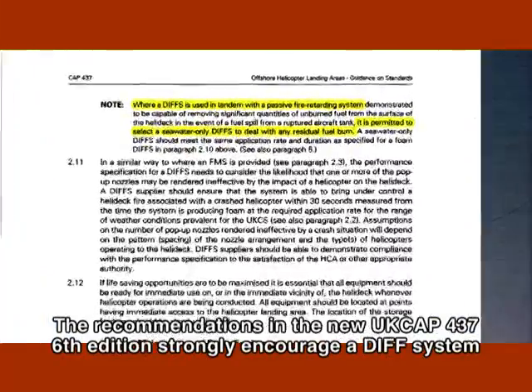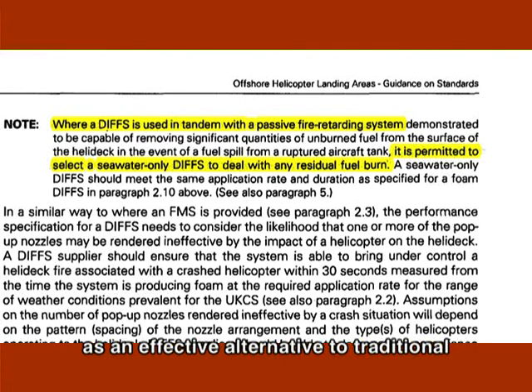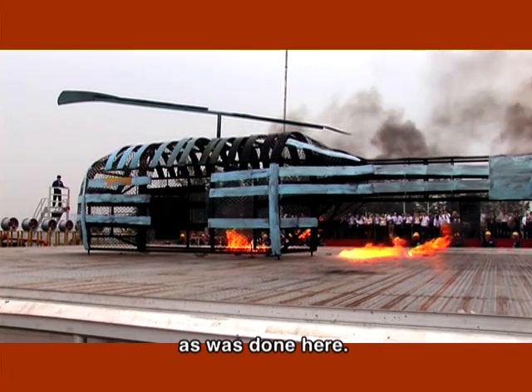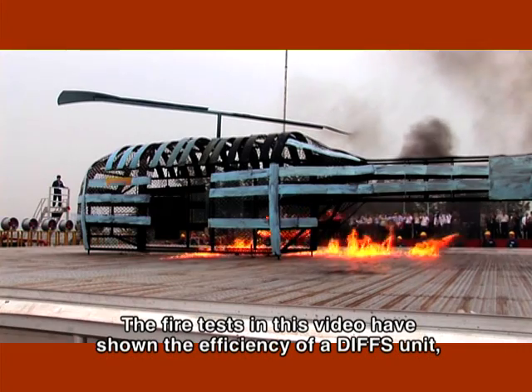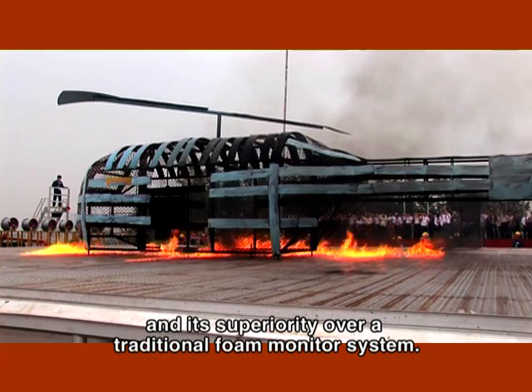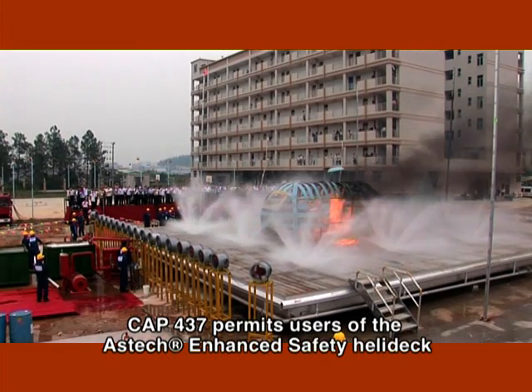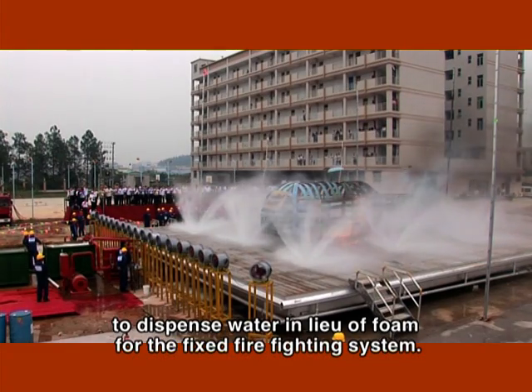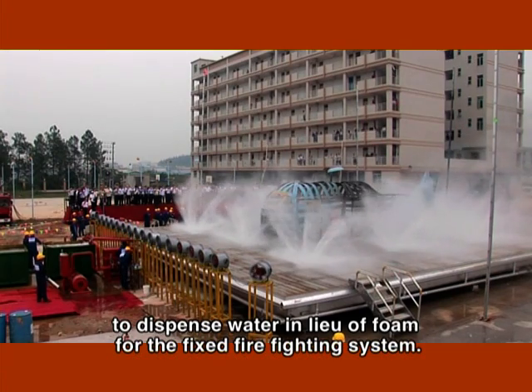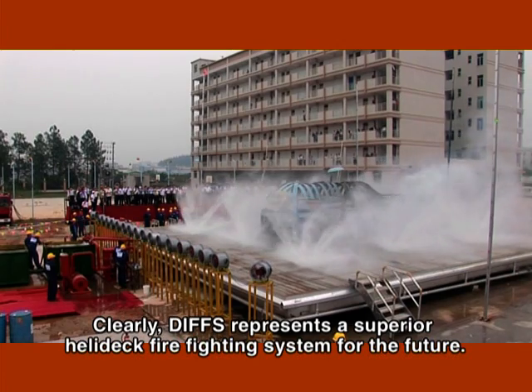The recommendations in the new UK CAP 437 6th edition strongly encourage a DIFFS system as an effective alternative to traditional foam monitors. They also require any DIFFS system to be performance tested, as was done here. The fire tests in this video have shown the efficiency of a DIFFS unit and its superiority over a traditional foam monitor system. CAP 437 permits users of the Astech Enhanced Safety Helideck to dispense water in lieu of foam for the fixed firefighting system. Clearly, DIFFS represents a superior helideck firefighting system for the future.